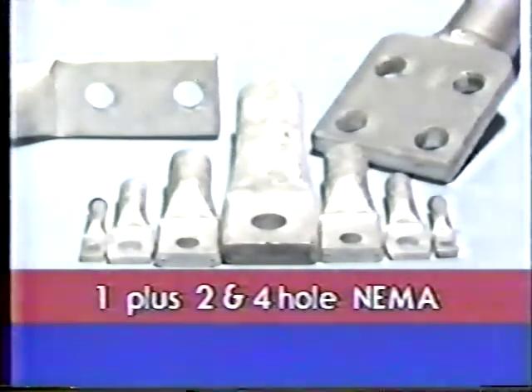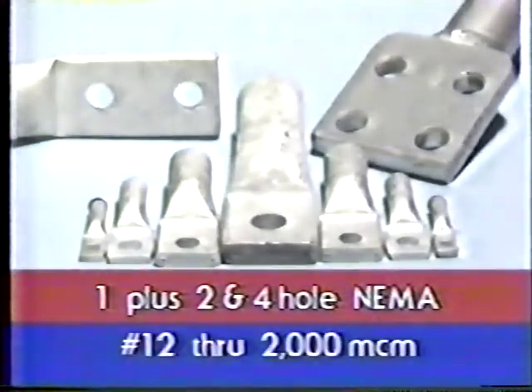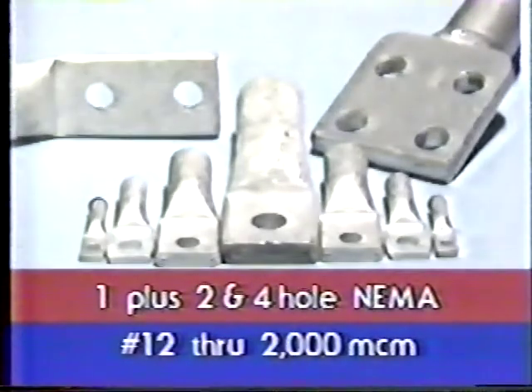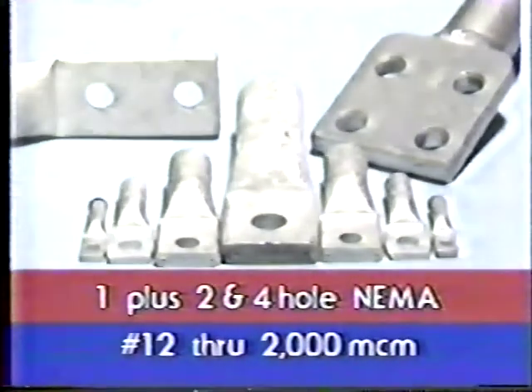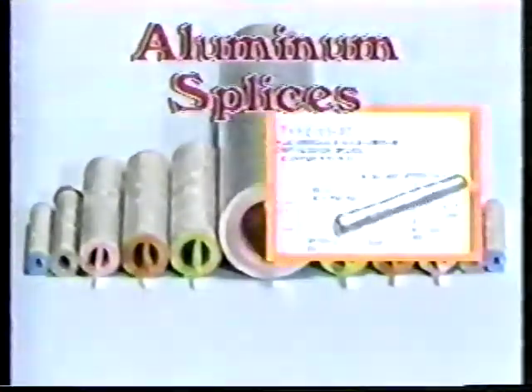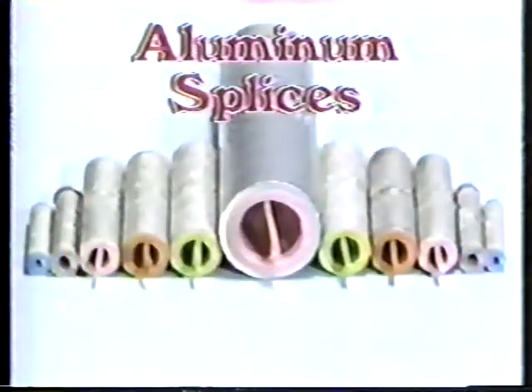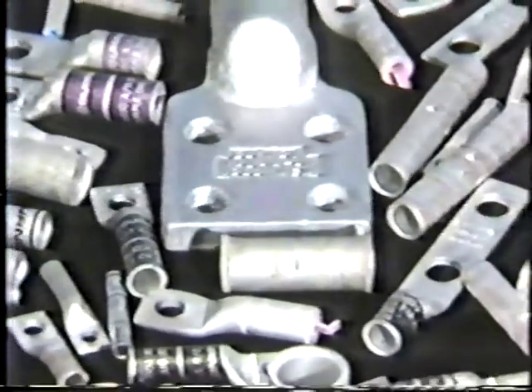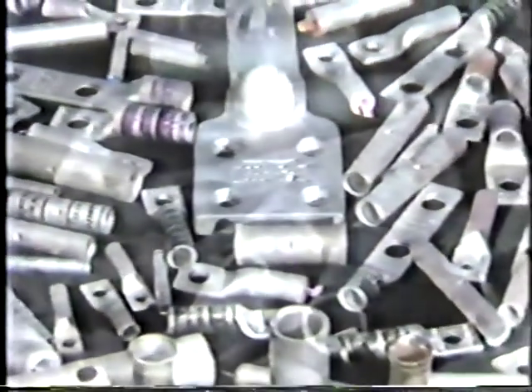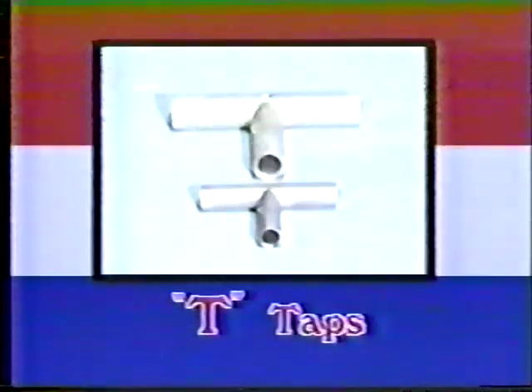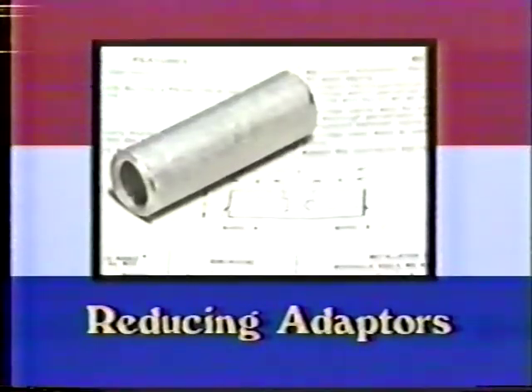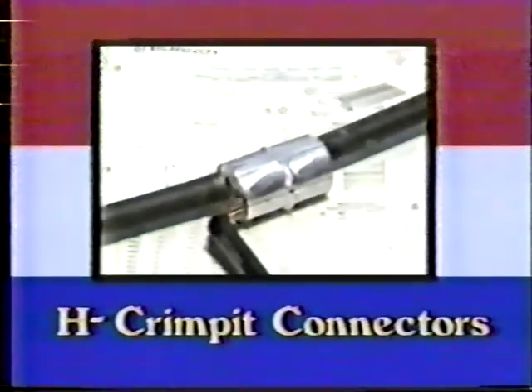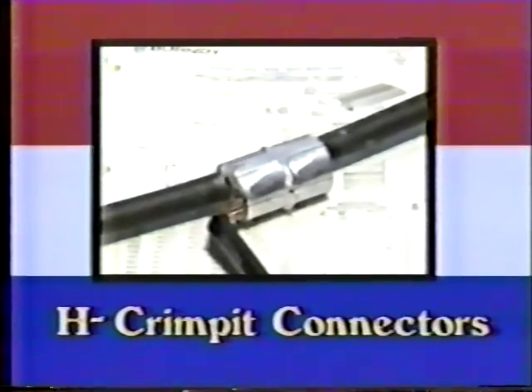Burndy's aluminum terminals are available in single, plus 2 and 4-hole NEMA versions, covering the full range of number 12 through 2,000 MCM. We also provide a full range of standard splices, as well as tapered versions for high voltage applications. The Burndy compression product line is extensive. In addition to terminals, splices, and installation tools, we offer a broad scope of related products such as T-taps, reducing adapters, compression taps, and a full range of connectors for making parallel and tap compression connections in risers and gutters.